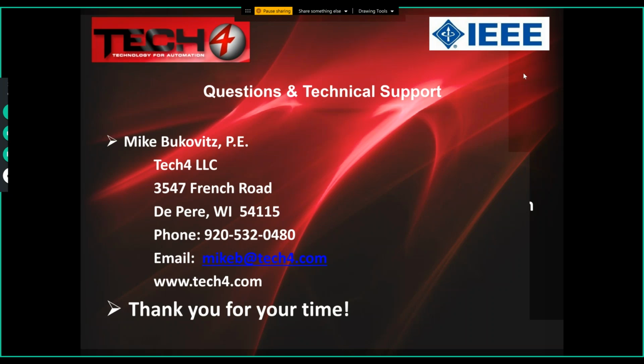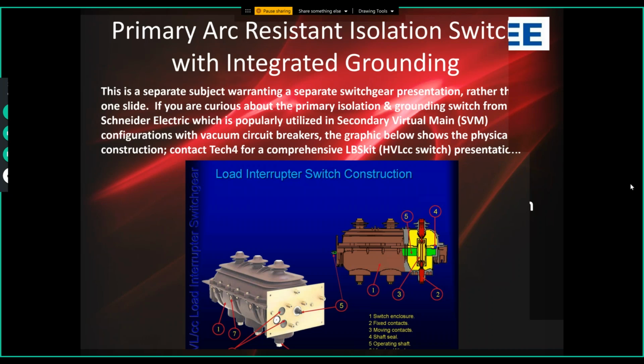There is one of the things Raj added. That's a very good point, Raj. He replied to Mariano, where the 87T is for internal faults. So you're obviously comparing the current in one side of the zone to the other, and if they don't match after you account for the voltage difference, obviously that current's going somewhere else, and it is faster. Differential protection is one of the approved methods of arc flash mitigation under 240.87 in the National Electrical Code. That's very good. Great questions.